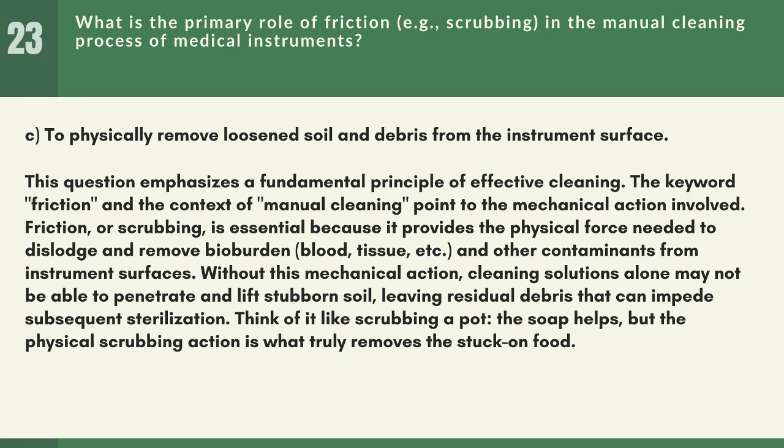Answer: C. To physically remove loosened soil and debris from the instrument surface. This question emphasizes a fundamental principle of effective cleaning. The keyword friction and the context of manual cleaning point to the mechanical action involved. Friction, or scrubbing, is essential because it provides the physical force needed to dislodge and remove bioburden, blood, tissue, etc., and other contaminants from instrument surfaces.